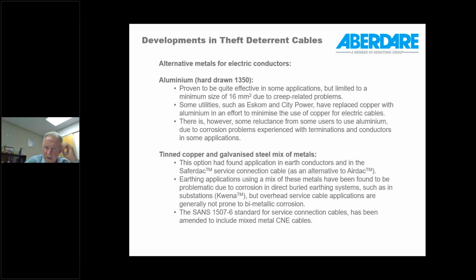So earthing applications also use a mix of metal. In some cases, you might know the Kwena product, which is a sort of braided product making use of tinned copper and galvanized steel, and that has been, let's say, fairly well accepted in the market. Although for direct burial applications, it's proven to be, let's say, problematic through bimetallic corrosion. But yeah, there are applications where these cables are also insulated.